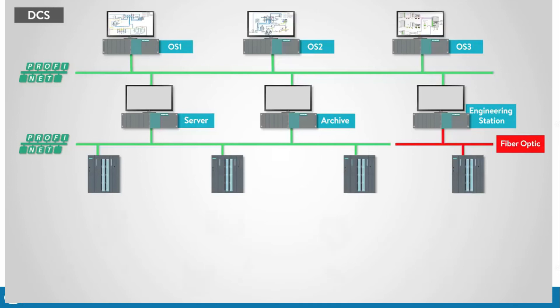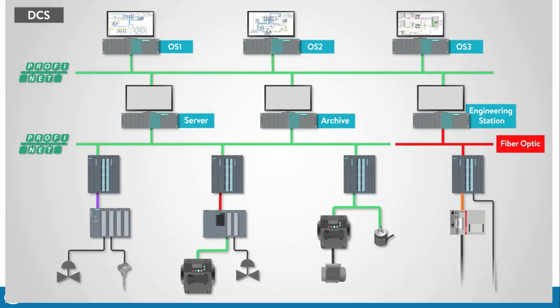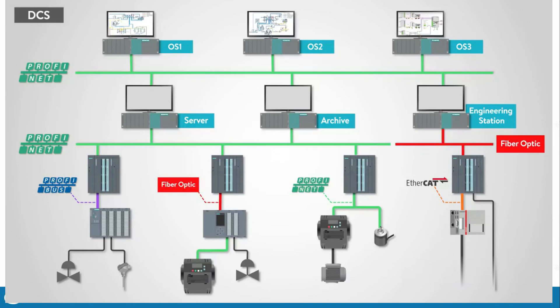The next level is the field device level. Communications between this level and the processor level can be nearly any type compatible with the components, including industrial Ethernet, Profibus DP, EtherCAT, fiber optic, or other proprietary communication protocols. Components at this level would be devices such as transmitters, switches, valves, motors, remote or distributed I/O, and more.